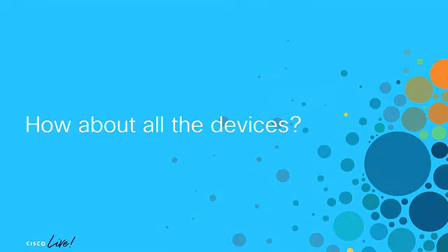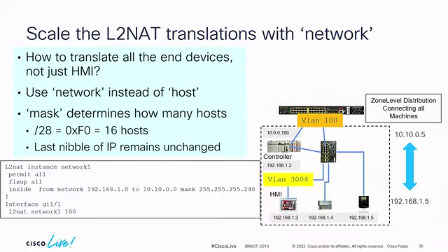All right. So the question that came up earlier was, can I do networks? Excuse me, one question. Yes, sir. Is HSR also supported on the ring? No. Sorry, no, because HSR is actually done in the same hardware component that is doing the natting. So we have an FPGA on the switch that does the layer 2 natting, as well as doing HSR, and they don't work together.